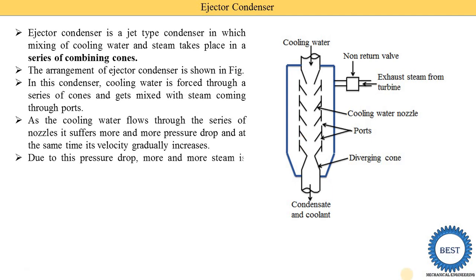Due to this pressure drop, more and more steam is drawn through the ports and gets intimately mixed with the cooling water jet and condenses there. When the cooling water passes through the nozzle, the pressure is dropped. When the pressure drops, the steam is drawn from the ports. When the steam is drawn through the ports, the steam and water mix and the steam is condensed.